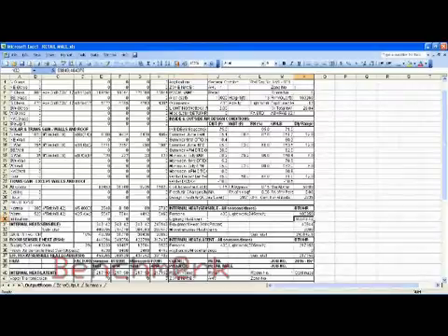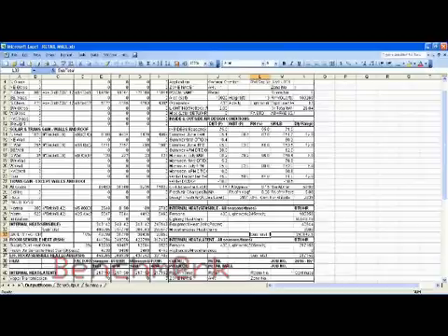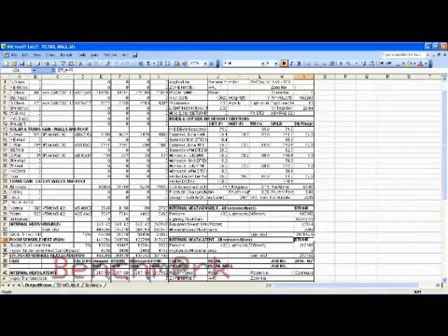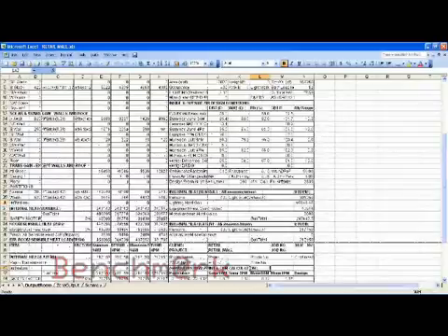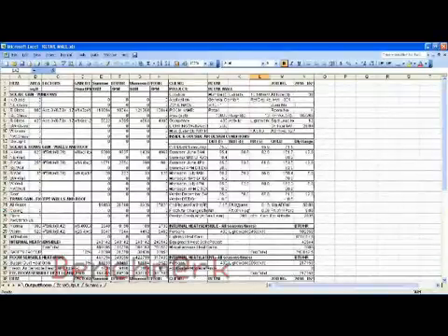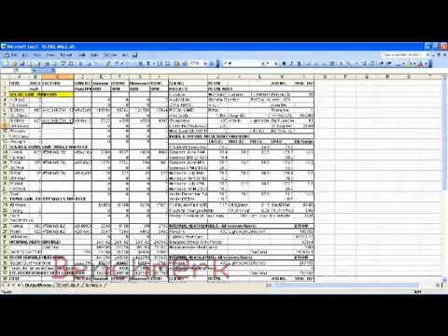In this case we are getting room sensible heat. We are using people and lighting sensible heat, as seen in the Part 2 section. We get effective room sensible heat by adding all these values — persons, lighting, and equipment load. For latent heat, along with fresh air, we get the effective room latent heat.